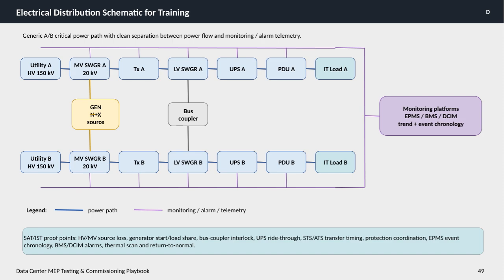This dual A-B path ensures redundancy and reliability, allowing continuous operation even if one side experiences a failure. In addition, a generator setup with an N+X configuration provides backup power to maintain uptime during utility outages. The bus coupler plays an important role in connecting these paths and managing power flow, while various monitoring platforms like EPMS, BMS, and DCIM track trends, events, and alarms in real time. The legend helps distinguish power paths from monitoring and alarm telemetry, emphasizing the importance of both for system reliability.